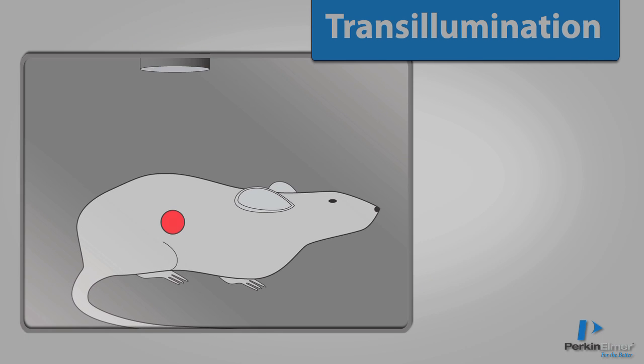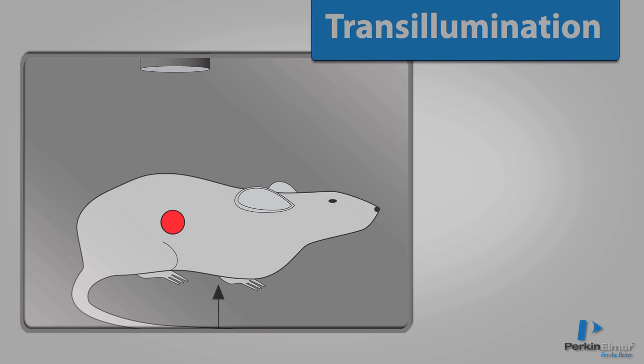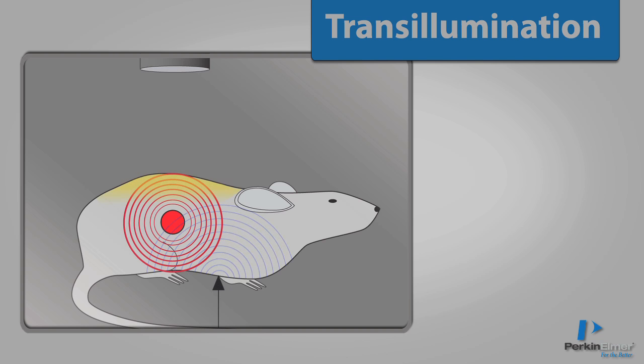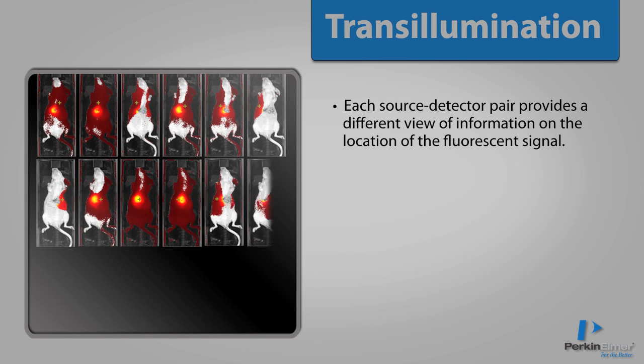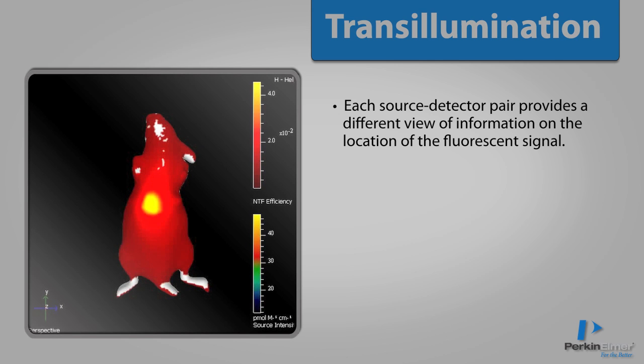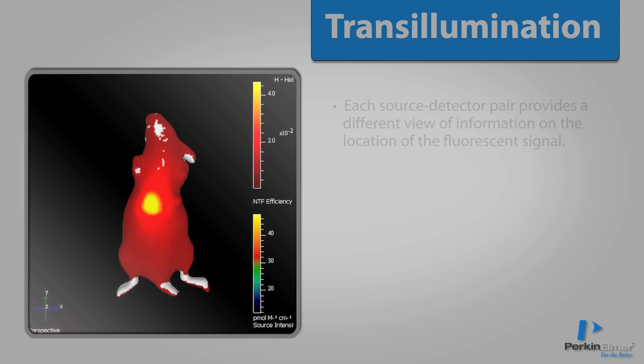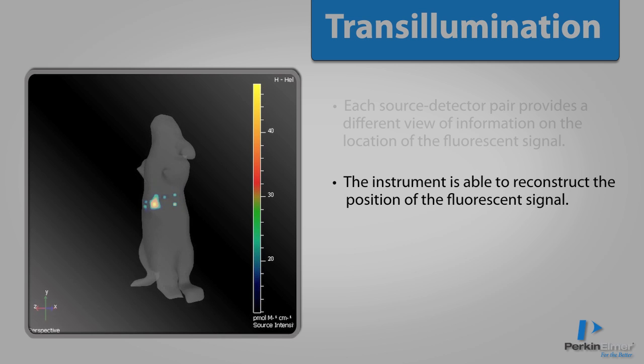In transillumination raster scanning, a light source moves from point to point, exciting the animal from below, which produces fluorescence emission data that can be detected from above. Each source-detector pair provides a different view of information on the location of the fluorescent signal. Using software algorithms based on complex tissue diffusion properties to combine these source-detector pairs along with the surface topography, the instrument is able to reconstruct the position of the fluorescent signal.